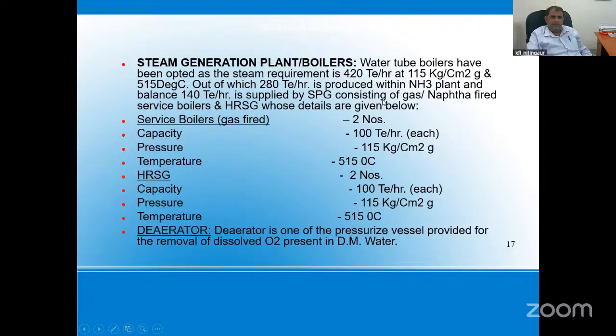In our plant, actually 420 ton per hour of steam is required to run the plant. Total 420. But out of this, 280 ton per hour is produced within the ammonia plant. The ammonia plant itself produces steam as and when it is running at full load. During the startup period, there is no production of steam in the ammonia plant, and all the steam is transferred to the ammonia plant from the utility section. When the plant is running at full condition, the total 280 ton per hour coming from the ammonia plant is sufficient to run the turbines at the ammonia section.